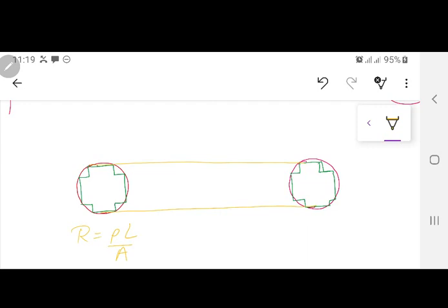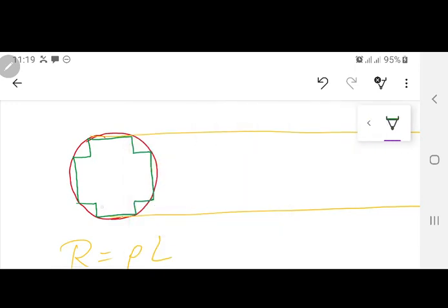Now the question arises: क्या yoke को भी circular करें? क्या yoke के ऊपर कोई winding आनी है? It's just a subdivision part. So technically speaking, there is no advantage of making the yoke circular. It can be just a rectangular piece of laminations joined together. If I zoom in over here and I want to draw the laminations, inside the limb you will see the laminations like this.